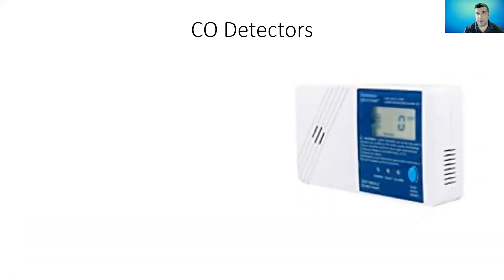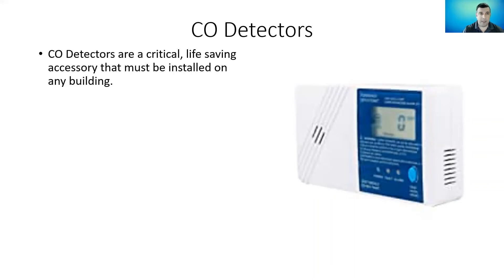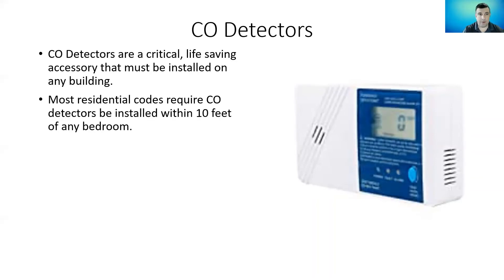Let's talk about carbon monoxide detectors — the ones we install inside a building. They are critical. We need to make sure we're installing them in any building, even ones that don't have fuel burning equipment, because as we've learned, a car idling in a garage or a portable generator can cause a carbon monoxide hazard. Most residential codes now require carbon monoxide detectors to be installed within 10 feet of any bedroom — because that's where people are asleep and not aware of carbon monoxide issues. If they were awake, they'd notice nausea and headache, but when asleep they may never detect it and may never wake up.